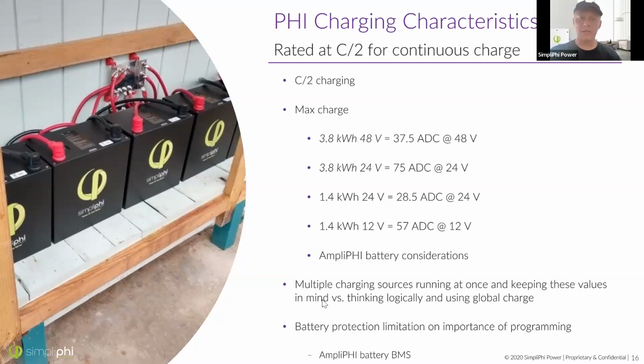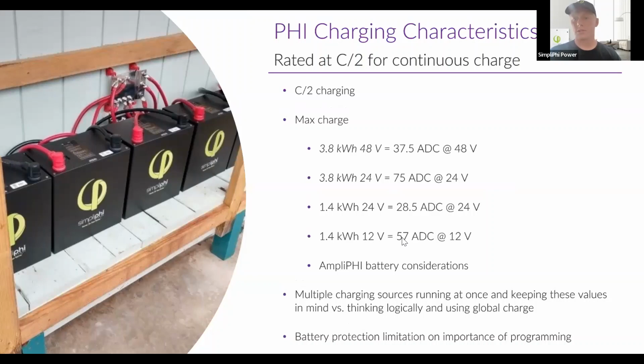One thing to keep in mind is if you have multiple charging sources on a system. So let's say you've got an inverter that charges at 6 kilowatts, and then you've also got a charge controller that takes solar power and converts it to the correct battery voltage and charges it at 2 kilowatts. It is entirely possible, unless you've disabled that feature, for both of those devices to charge at once. So unless you're able to cause those two devices to communicate and make sure they don't charge at the same time, you're going to want to make sure you have a battery bank large enough to handle that full 8 kilowatt charging capability.